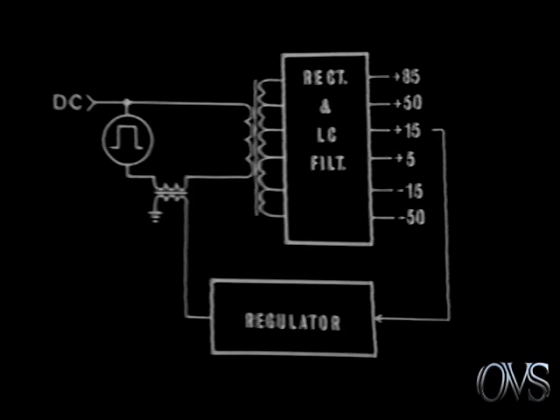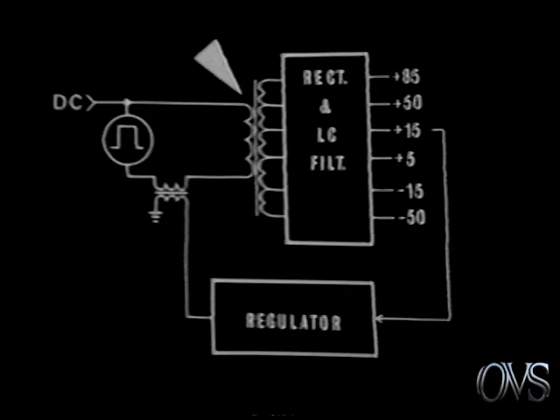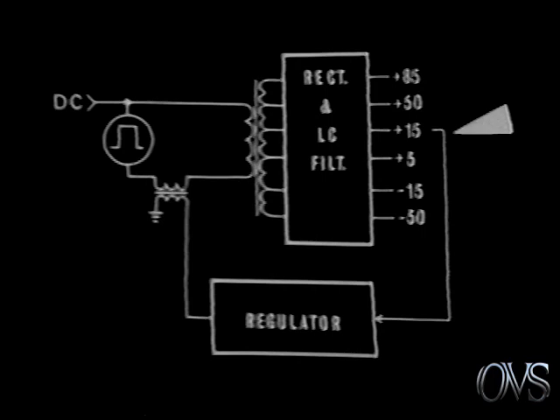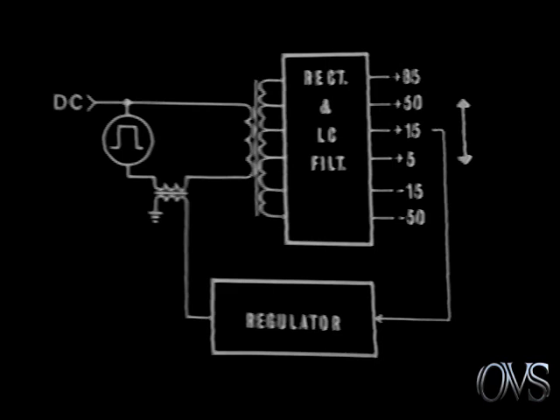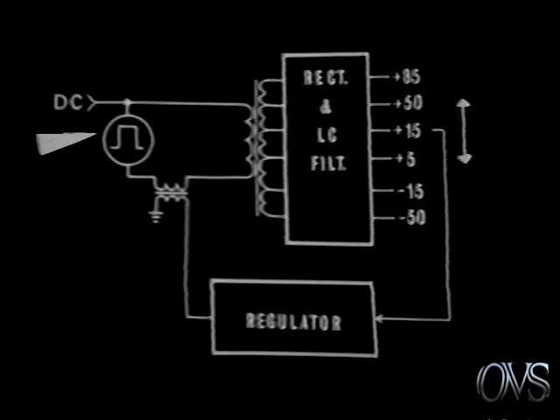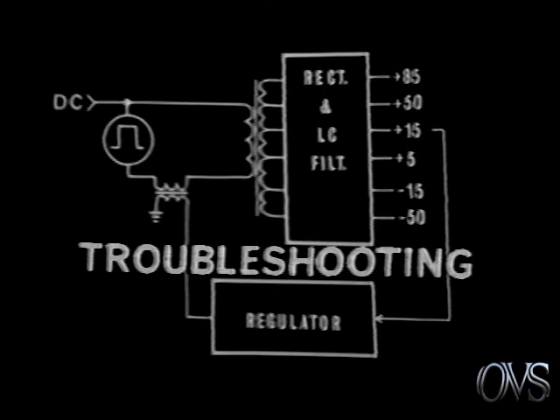An oscillator in the converter changes the DC to a rectangular waveform. This AC is then coupled through a power transformer to a rectifier filter. Secondary taps provide the AC levels required for each DC output. The plus 15 volt output is used as a regulator reference. Any variations in the plus 15 through the regulator change the saturation level in a transformer. This saturation level in turn changes the frequency and duty cycle of the oscillator. This oscillator therefore tracks the plus 15 output. All outputs are thus maintained at a specified level.